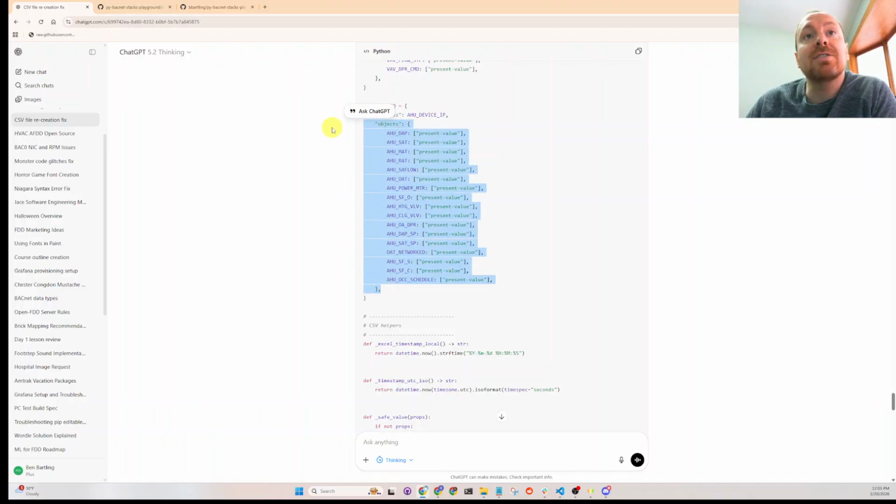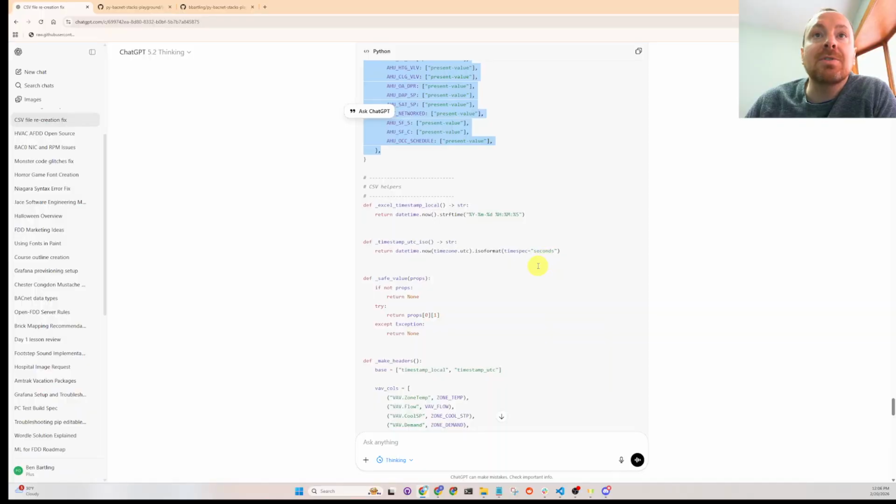We should be conscious that we're not requesting 140 points every minute, every possible point, because most of the data is worthless, and it clogs up a lot of network congestion and everything. So if you want to keep your BACnet network healthy, don't request every point on the building automation system, in my opinion.